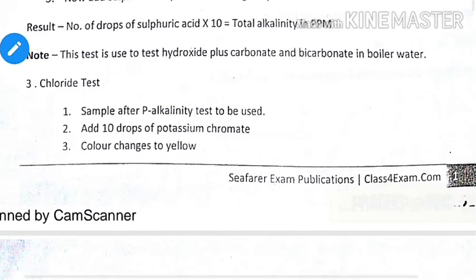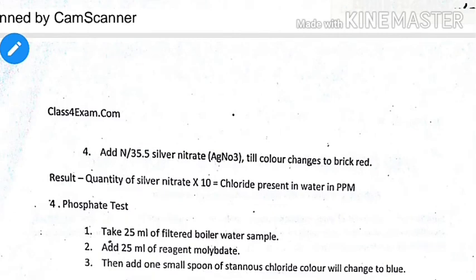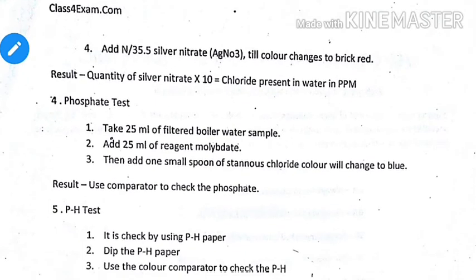For the chloride test procedure: take a 1 mL boiler water sample and add 10 drops of potassium chromate — color changes to yellow. Then add N/35.5 silver nitrate until the color changes to brick red. The quantity of silver nitrate multiplied by 10 equals the chloride present in water in ppm.